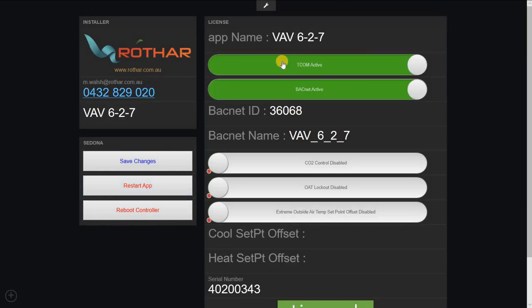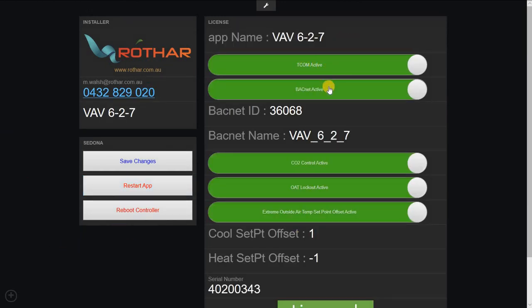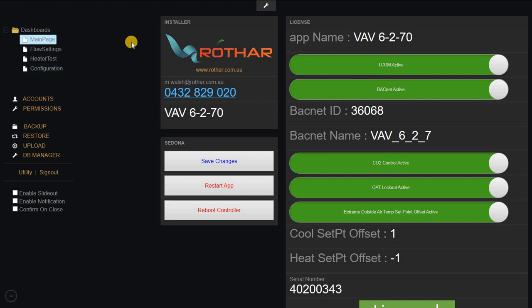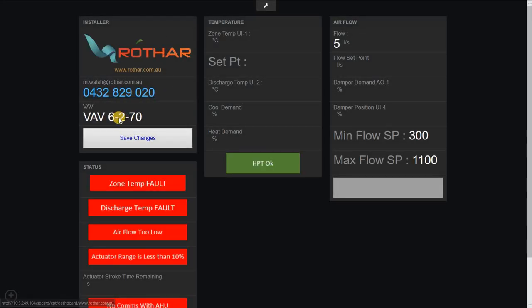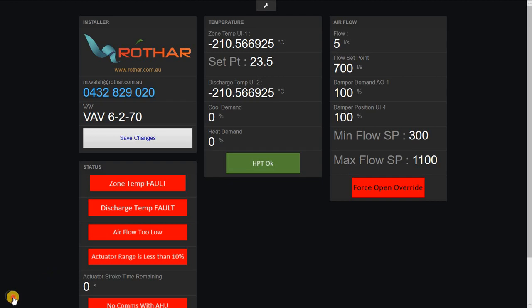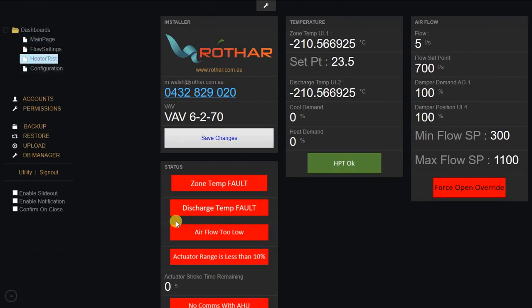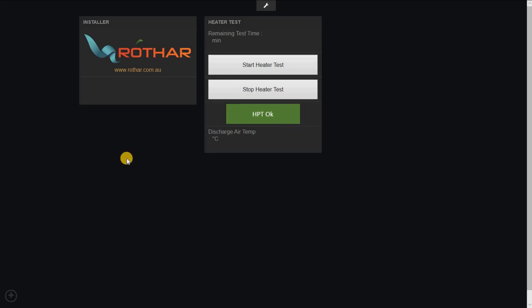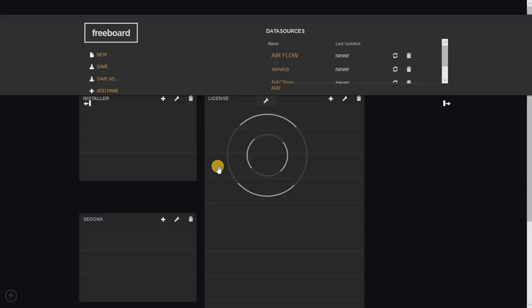On this page, you can set whether to use TCOM or not, whether to use BACnet or not. You can rename the application. So if we wanted to call this VAV 6-2-70, change this application name, and it changes through the whole program. The main page. The new name is 6270. That will be on every page. That way you know which VAV you're on. You only have to change it in one place if you're renaming things.